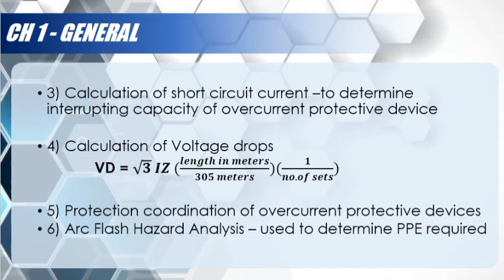Then, next we have the calculation of voltage drops. So, stated here or shown here is the formula for voltage drop, which is equal to square root of 3 times the current and impedance multiplied by the length in meters all over 305 meters times 1 over number of sets. Then next we have the protection coordination of overcurrent protective device. And lastly, under design analysis is the arc flash hazard analysis. So this is used to determine the PPE required.